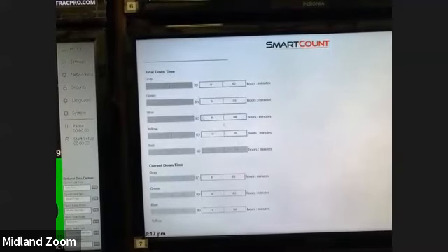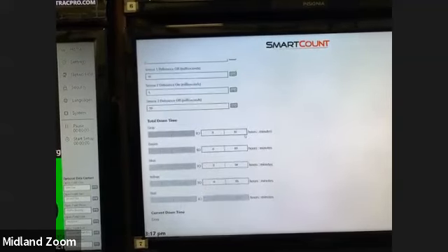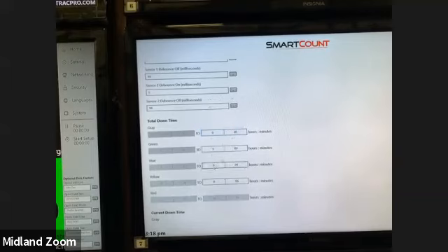These boxes here for total downtime, you'll see the gray, green, blue, yellow, red, current downtime. These are the different thresholds that you can set. Let's say for total downtime, the customer really doesn't care if they have any downtime until 5 minutes. So you could set all of these values to 0 just by clicking on the box, clicking on the number, and then making sure you click the check mark to save it. If I did that on all of these, the only color I'll ever see is going to be the gray and then the yellow. I'm sorry, you're going to see the yellow and then the red.